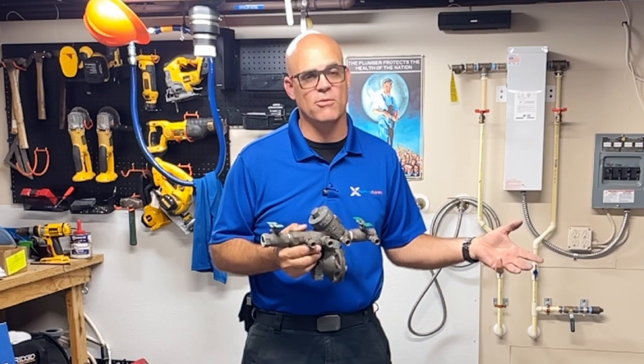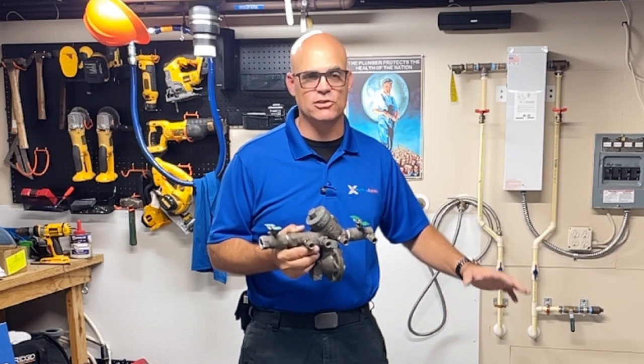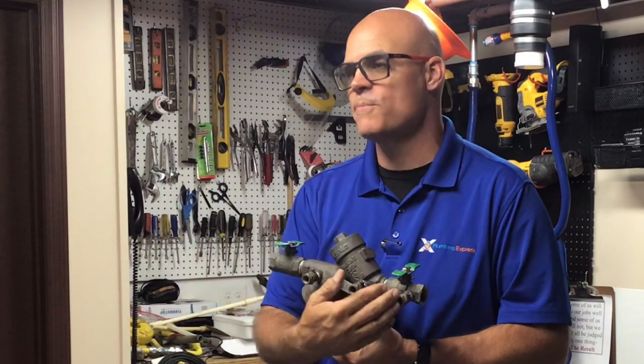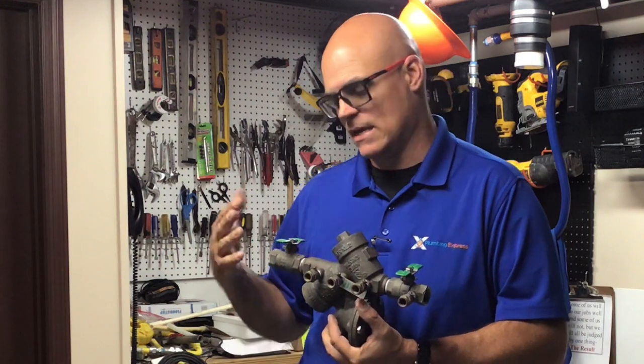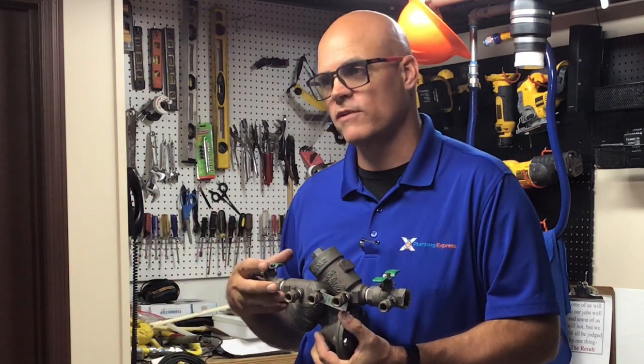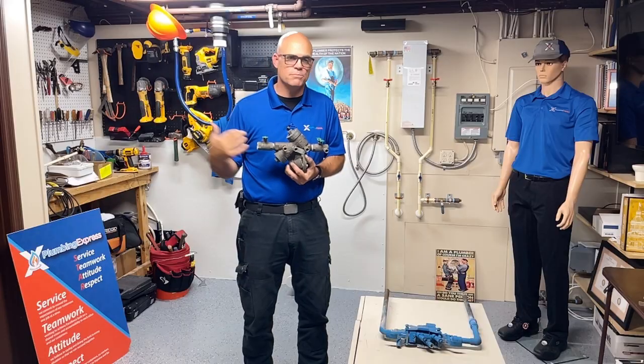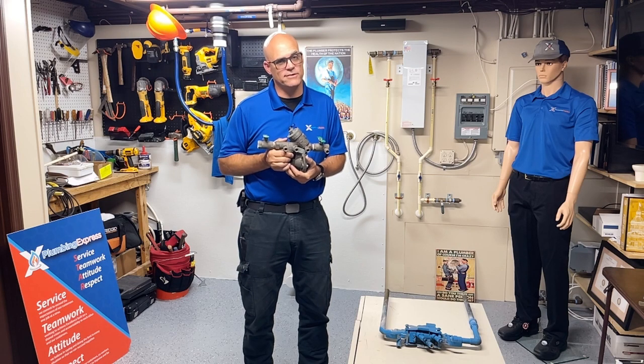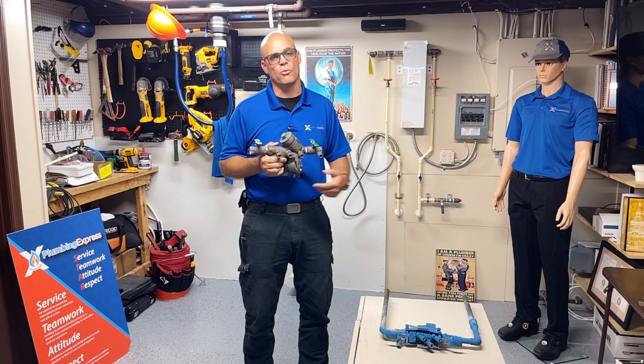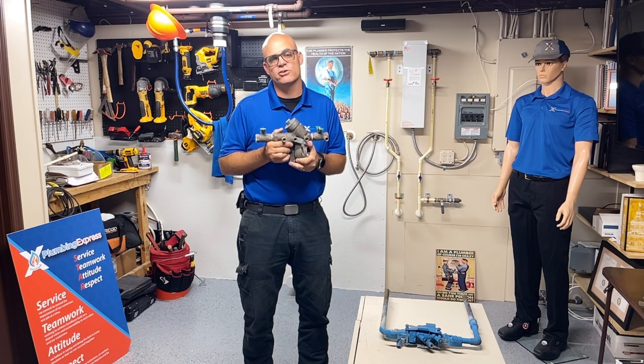What we don't want is to allow a backflow to occur. That could mean there's a fire — the fire truck comes out and has to pull water from a fire hydrant — or there could just be a break in the road or in your yard. Whenever that happens and pressure is lost, it can cause a back siphonage that pulls water from your house out into the main. If you've been putting chemicals into your water system for photography, or fertilizer, pesticides for your irrigation — it pulls back into the main, maybe into your neighbors' supply, possibly reaching a school down the road or a workplace. It's just a very dangerous situation.